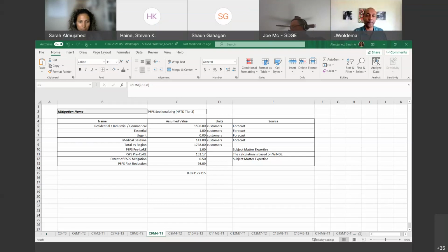Second, a follow-up question: in those instances where there are changes to the recloser settings, would the resulting settings result in a higher potential incidence of fires or electrocutions as a result of those changes on sections upstream of the recloser or sectionalizer? The answer is no additional risk or higher risk associated with adding a sectionalizing device.